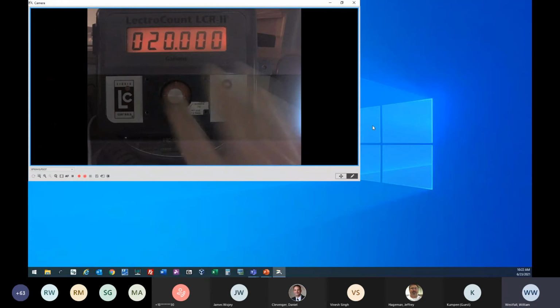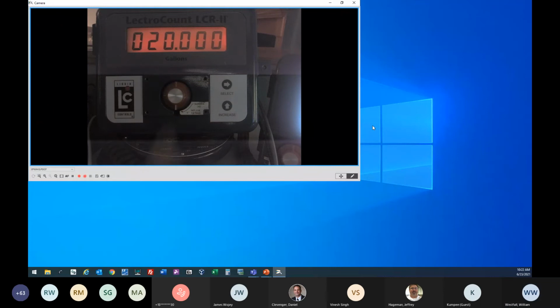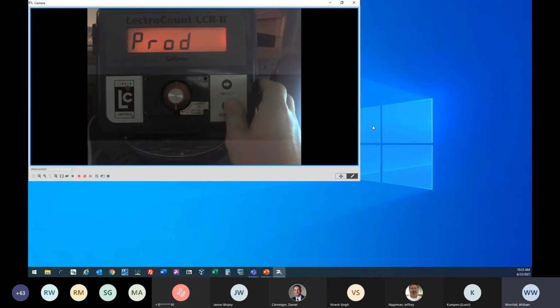What I'm going to do is unplug my lap pad. My lap pad's unplugged, and now I just have a standalone register hooked up to the printer. Again, take your faceplate off, with the red knob in the 6 o'clock position and the little white line down towards the bottom. You hit your select key, and it's going to flash. This is asking you what product you want to deliver. If you look, I'm pushing the increase button, but it's not going anywhere. The reason is that I've only got a K factor in one product, so it's only going to allow me to calibrate those products that already have a K factor in them.